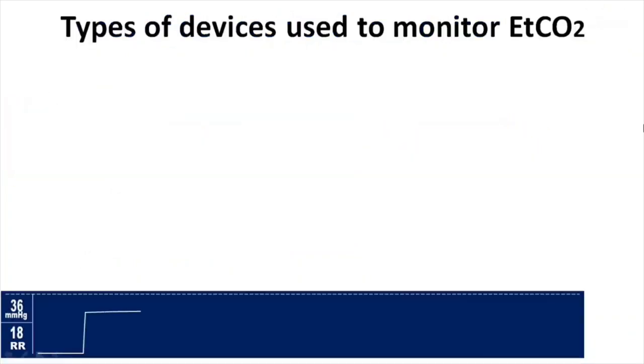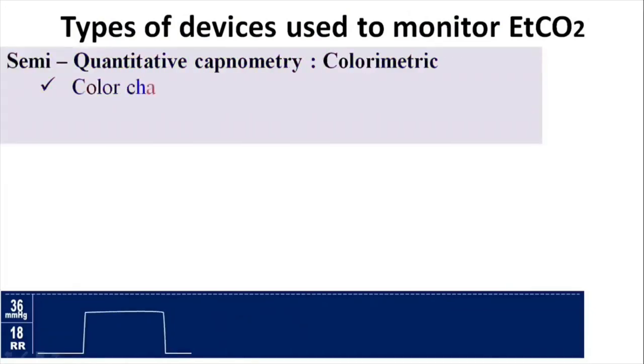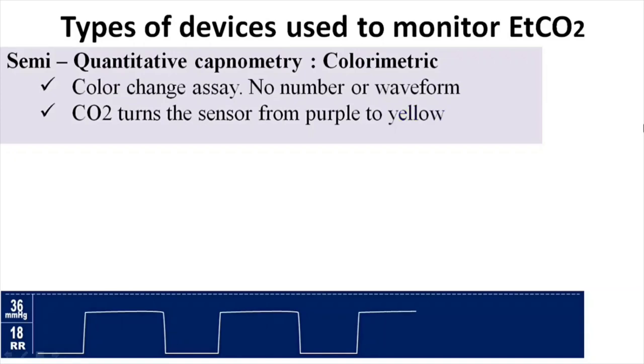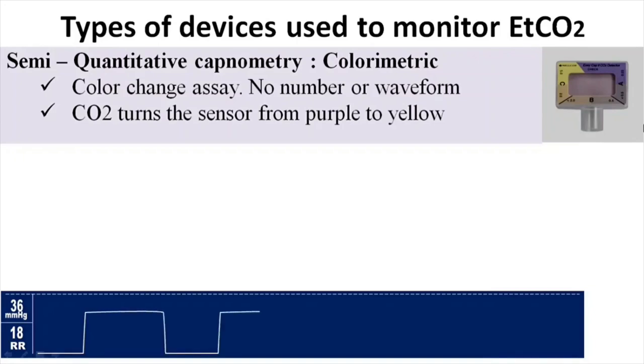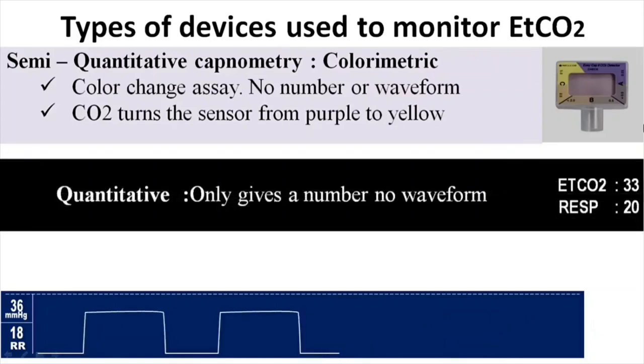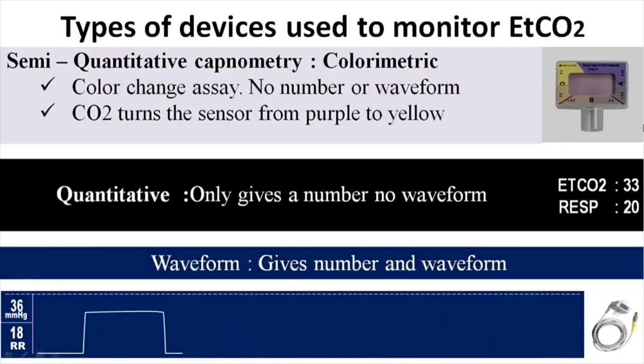There are different types of devices used to monitor EtCO2. Semi-quantitative capnometry includes the colorimetric EtCO2 detector, which contains a color-change assay — purple, tan, and yellow — with no number or waveform; it only indicates whether EtCO2 is present or not. Quantitative capnometry gives a number only with no waveform, while full quantitative capnography gives both waveform and number.